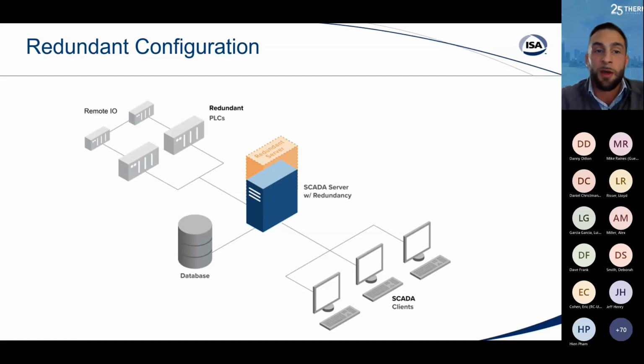The next configuration is a more redundant setup. It's the same configuration as we started with, but now built out with redundancy at different levels. Here we have redundancy at the PLC level, with the same distributed remote I/O at the facility, connected using a fault-tolerant network, so if there's any break in the network infrastructure, they can still communicate with all of the I/O. If either PLC were to go down, the other picks it up as a hot standby.